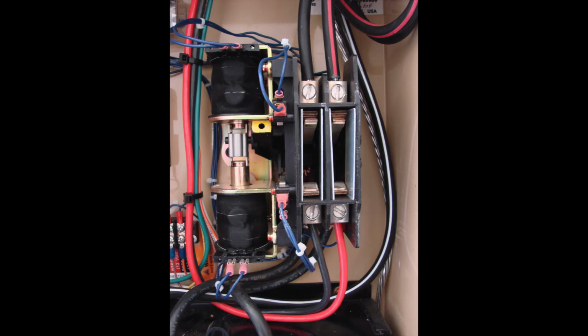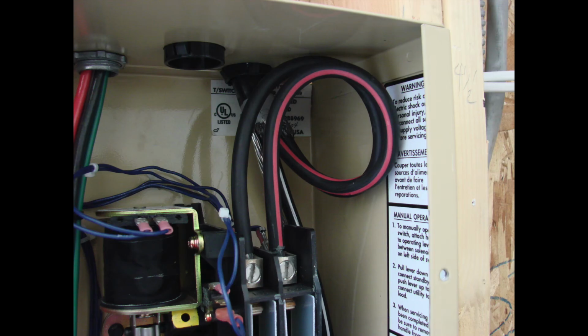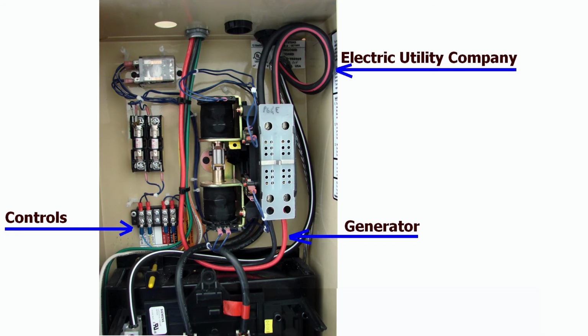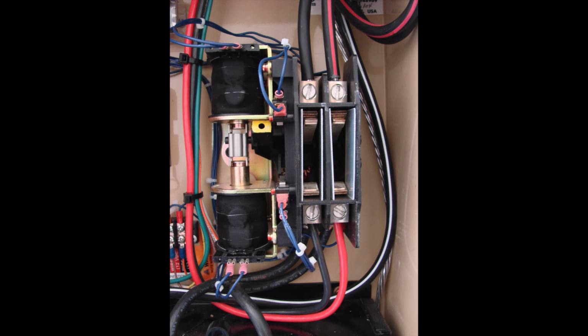But we come in with a loop of wire, we curl it, and we bring it in through the line section at the top of this transfer switch. You'll see there are a pair of lugs at the top for line coming in. And then we've got a pair of lugs at the bottom of this transfer contact mechanism, and that is where the 2 wires from the generator are attached. We have to take the safety guard off to attach these, and then we put the safety guard back on.